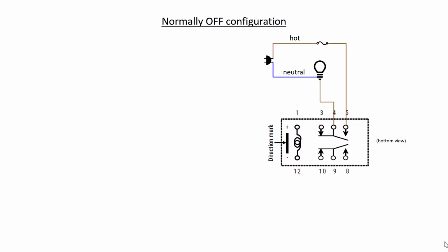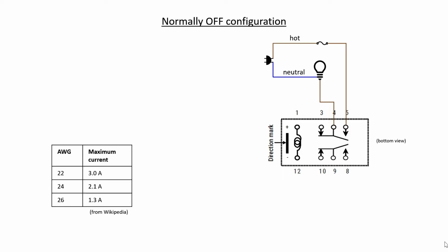Light fixtures installed in rooms everywhere in the world are switched on the hot side of a circuit only. Relays should also be installed on the hot side of the circuit for the same reason. I'm also showing a fuse here, and you always want the fuse upstream of everything else, so that if the current were too much, the fuse would blow on the hot side first.